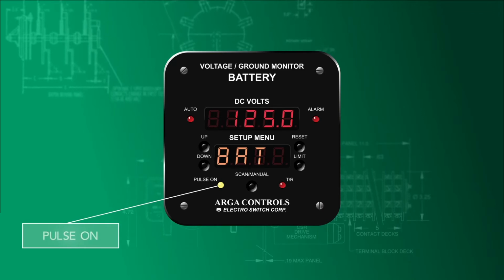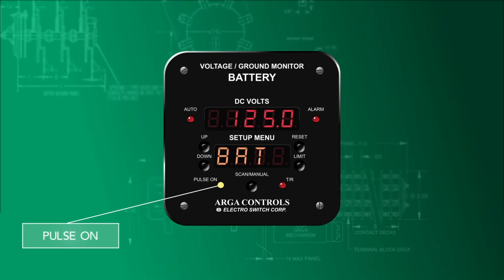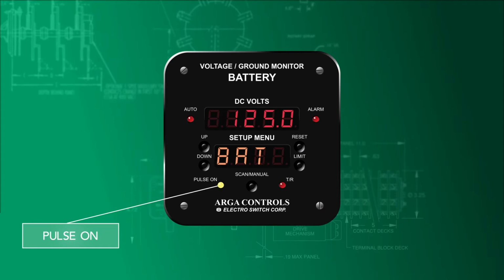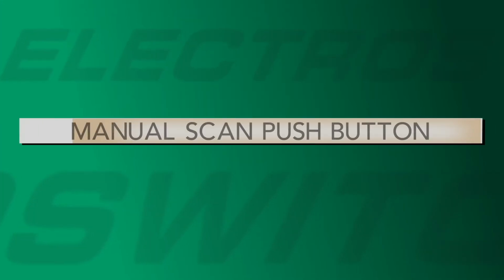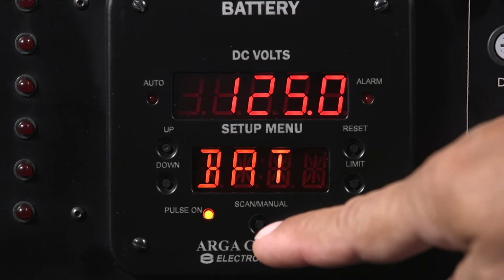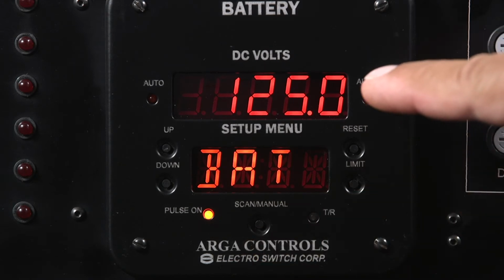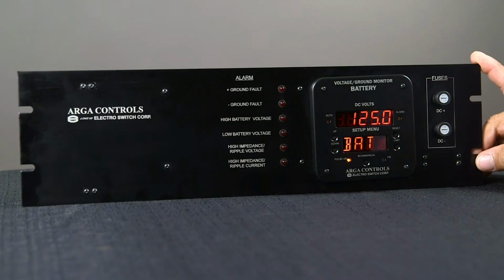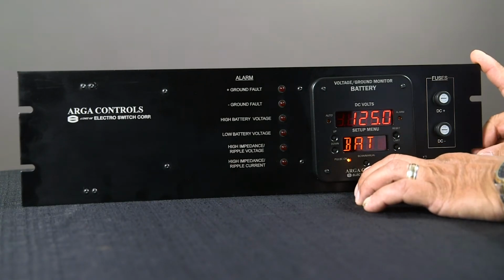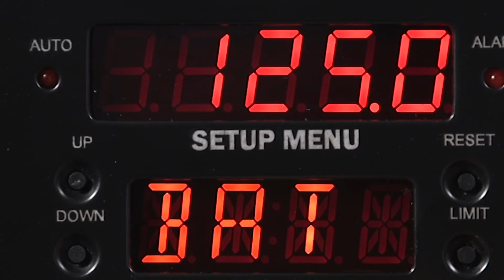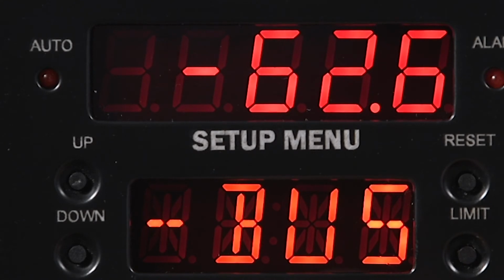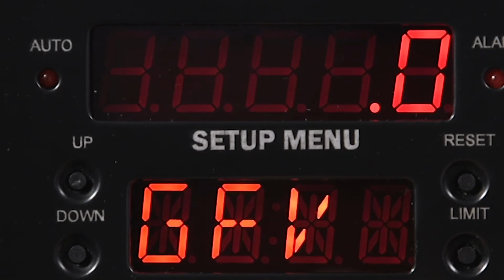Finally, a pulse on LED that is on when you're making use of the pulser and the handheld detector to locate a ground. As I stated, the manual scan push button allows an individual to view the overall battery voltage of 125 volts DC and then scan through the other various displays. By depressing, releasing the manual scan button, one is able to view the various available indications, including the positive side of the battery voltage, which is half the battery voltage on the positive and negative side, plus or minus 0.2 volts DC. The next view is a fault voltage indication, which is currently 0, because there is no ground fault.